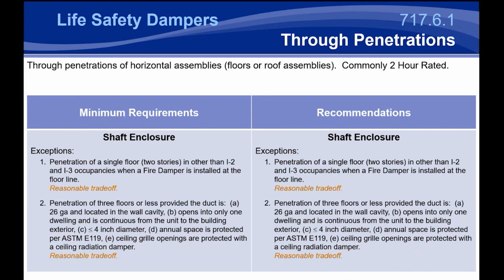Now, if you've got a through penetration where the duct penetration is going from one floor to another, typically you're going to have to put a shaft in place unless you can install a damper in that floor that protects that floor opening. All dampers mounted in floors have to be in concrete, non-load bearing floors. That's really the only option. There's no load bearing option for a stud application.